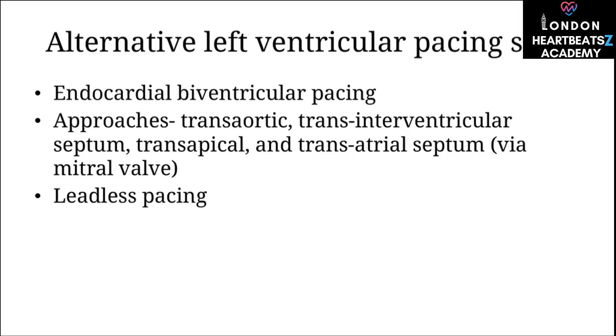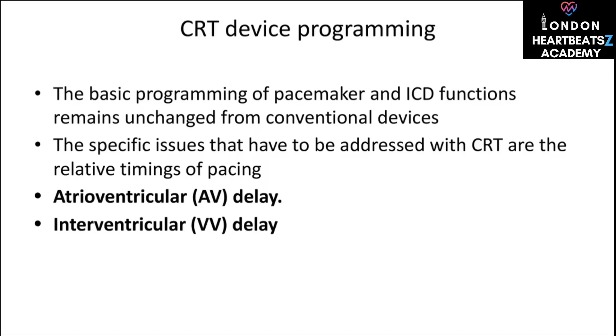Exactly. VV delay is the timing between the right and left ventricular pacing. Adjusting this aims to get the two ventricles contracting together more synchronously. Making the main pumps work together. How do they set these initially? Often, they start with default values, known to be general, say, AV delay 100 to 120 milliseconds, VV offset 0 to 20 milliseconds. Or they might use the patient's ECG as a guide, but it's crucial to reassess after a few weeks.